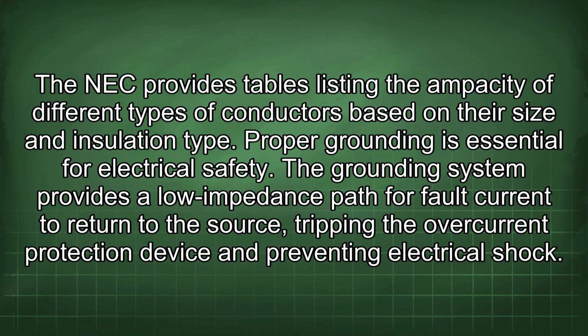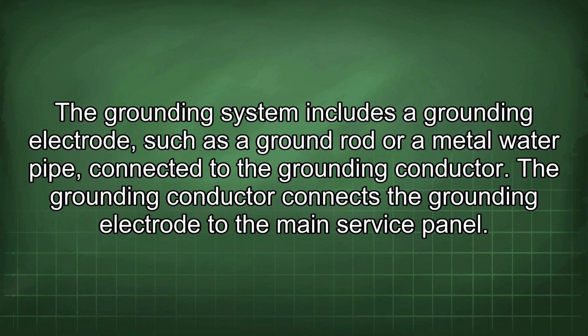Proper grounding is essential for electrical safety. The grounding system provides a low impedance path for fault current to return to the source, tripping the overcurrent protection device and preventing electrical shock. The grounding system includes a grounding electrode, such as a ground rod or a metal water pipe, connected to the grounding conductor. The grounding conductor connects the grounding electrode to the main service panel.